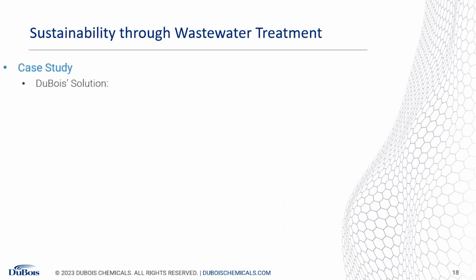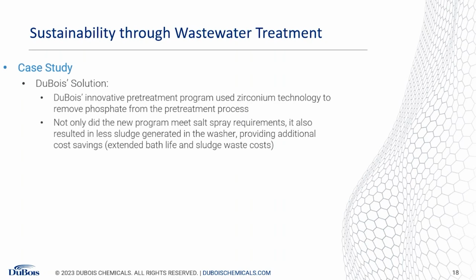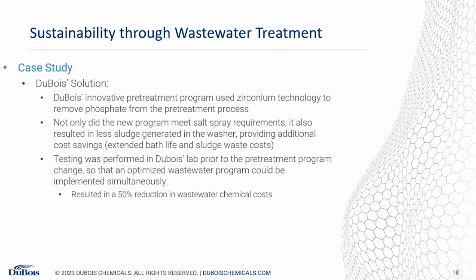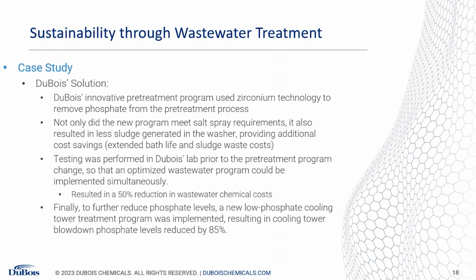Additionally, in the cooling tower we applied some of our innovative chemistries—we have a product that isn't phosphate-based. Phosphates are often used in cooling towers both as a corrosion inhibitor and a scale inhibitor, but our lower-phosphate product uses polymeric chemicals instead of phosphate to provide that same corrosion and scale inhibition. We were able to switch that and reduce the phosphate coming out of the tower by about 85%.